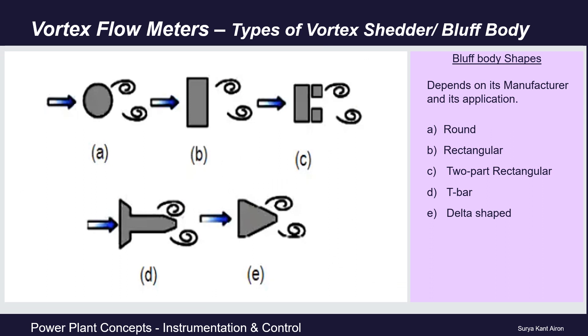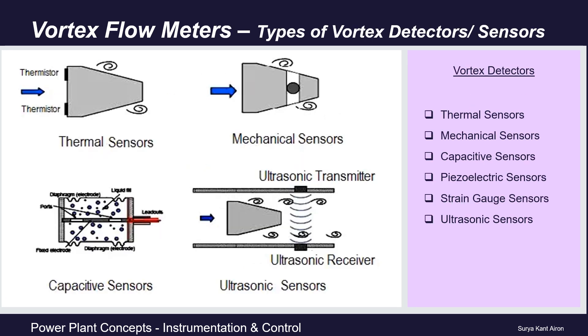The bluff body or vortex shedder shape and size differs from manufacturer to manufacturer and depends on the application. Various shedder shapes include round, rectangular, two-part rectangular, T-bar, or delta shape. Different types of vortex detector sensors are also available: thermal, mechanical, capacitive, piezoelectric, strain gauge, or ultrasonic sensors. The most commonly used are piezoelectric sensors.